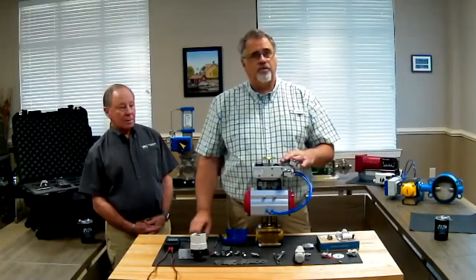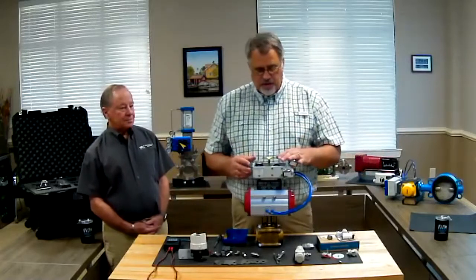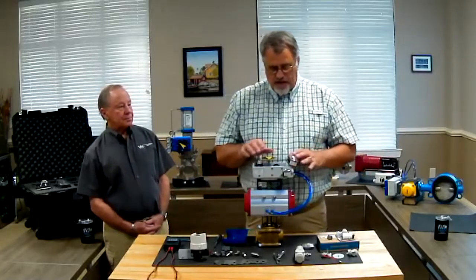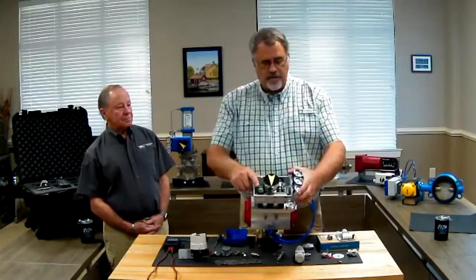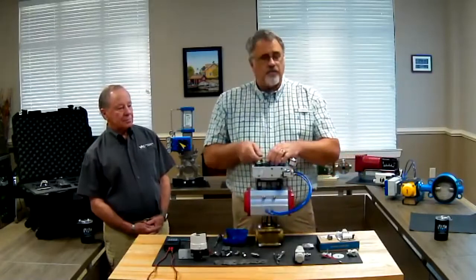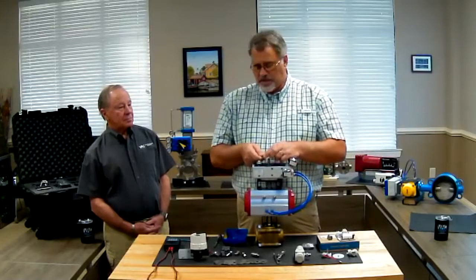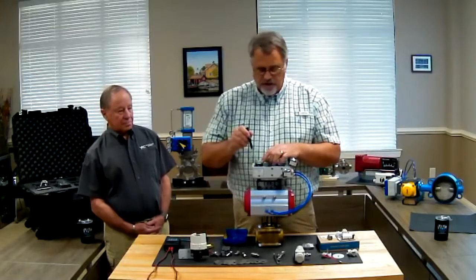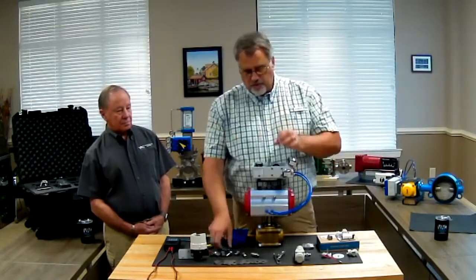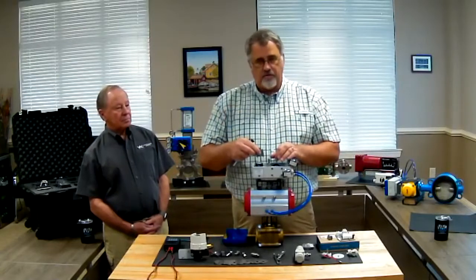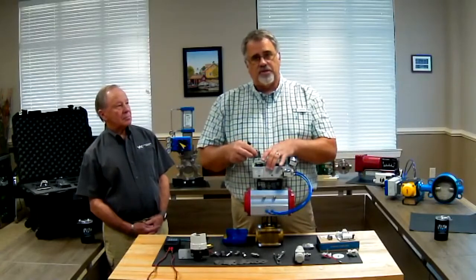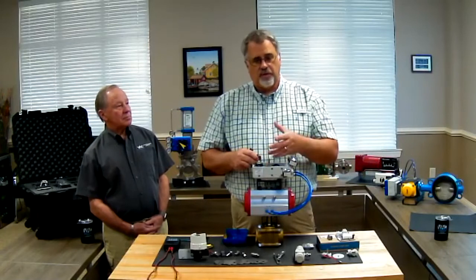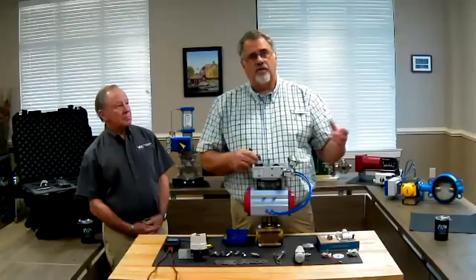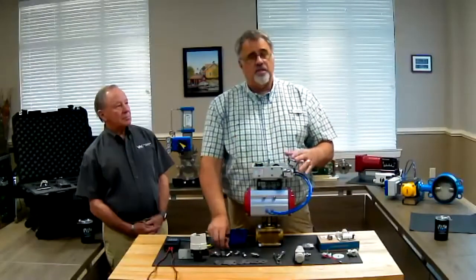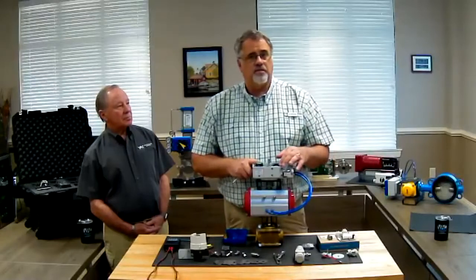So first thing we're going to do is talk about calibration of this unit. Okay, I've got this set up right here as an electro-pneumatic positioner. We've got an I2P in it, but if you wanted to convert this to a pneumatic, it's very simple with just a screwdriver. I can take these two screws out, pull the I2P out, and put this plate in its place. And now I've gone from a positioner that takes a 4-to-20 signal with an I2P in it, current to pneumatic converter, to a pneumatic positioner that accepts a 3-to-15 PSI pneumatic signal.